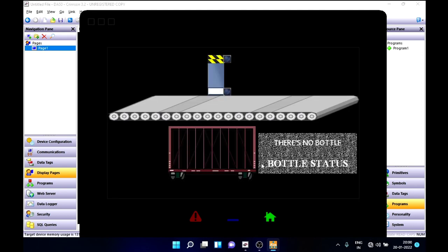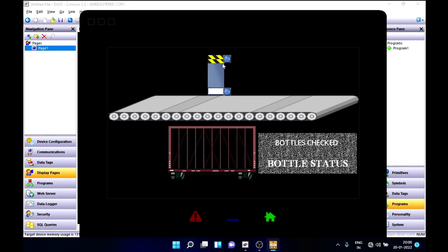As you can see, since both sensors are not sensing, our status is 'there is no bottle'. If I turn on the bottom sensor, the piston comes forward to position one to push the fallen bottles into the basket. If I turn on the top sensor as well, the piston goes back to its original position so that our conveyor has only standing bottles and our status becomes 'bottles checked'. If I turn off the top sensor again, the piston comes forward again to push the fallen bottles.